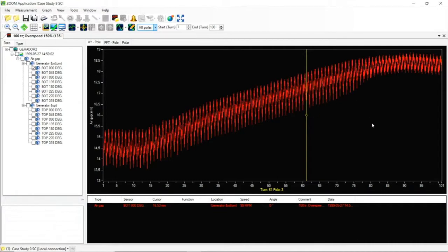The delta, of course, is the rotor shape. We can see how the rotor shape is slowly decreasing, but the circularity, which indicates distortion, remains somewhat high. Then during a couple of rotations, it actually goes back to its shrink fit—it settles. It's this result that the OEM, the utility, looked at and said, wow, the design works. It does exactly what it's supposed to: it floats to absorb the energies, allowing the rotor to go through this dramatic event, and when it slows down, it goes back to its original shape.